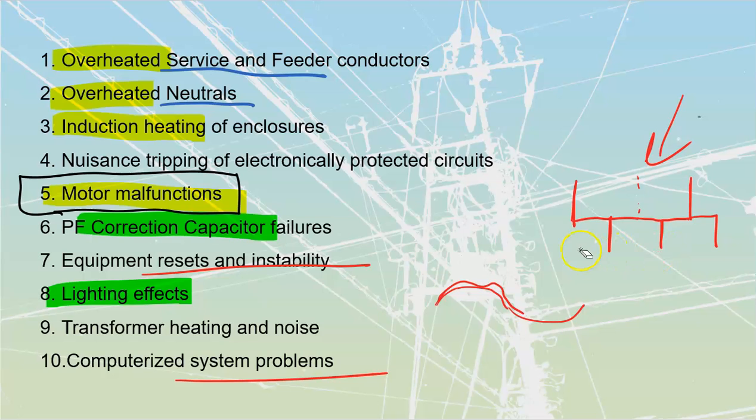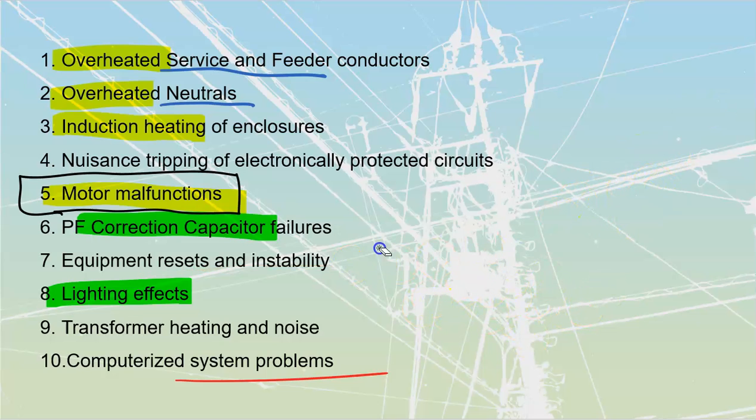Transformer heating and humming. Transformers are designed to transform power from one system over to the other, but that means they're also going to carry frequencies and currents, right? So if we have our third order or triplen harmonics and harmonic currents generated inside one of those sides of the transformer, whether it's on the supply side or on the load side, they're going to get passed through. And so we are going to get heating.